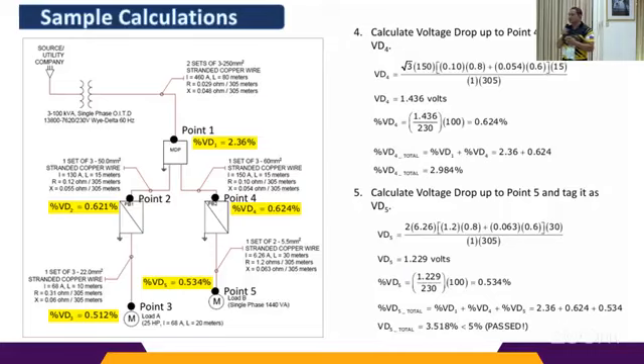So we total VD1, VD4, and VD5: 2.36 plus 0.624 plus 0.534. The voltage drop total at 5, coming from the supply, is 3.51%. That is less than 5%. Therefore the voltage drop passes, meaning our cable passed. So okay, but that is only for the design.